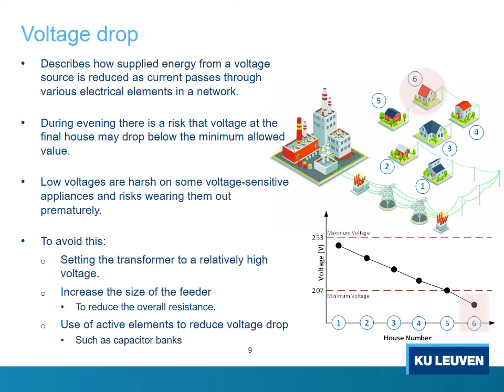Another solution can be to increase the size of the feeder, that is, to reduce the overall resistance on the entire network, and if you reduce the resistance, then you reduce the voltage drop. Another solution can be to use an active element such as capacitor banks at the substation where the main transformer is located.